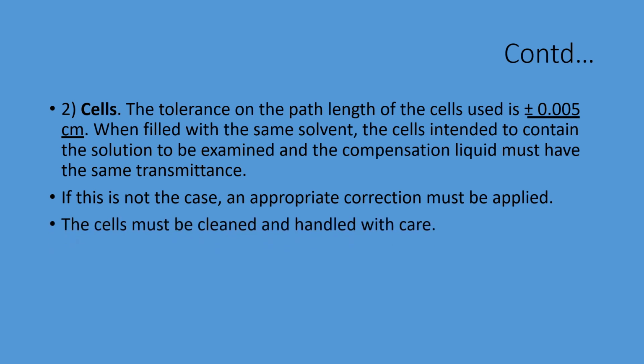The cells must be cleaned and handled with care. Cleaning of cells is very important. Never use strong acidic cleaning reagents like chromic acid for cleaning the cells. Use mild detergents. Soak the cells overnight in diluted mild detergent for better results. Also, never use broken or scratched cells. You have to store them well to avoid scratches on the light path, that is the clear side of the cells.